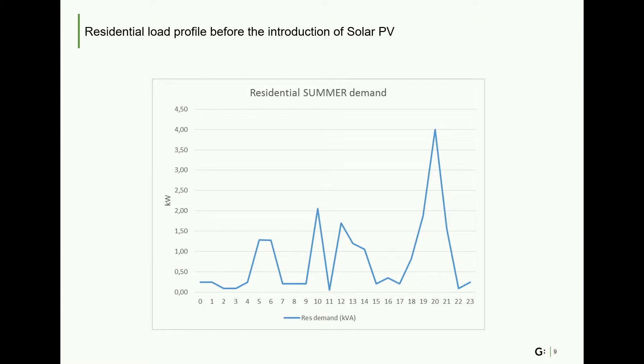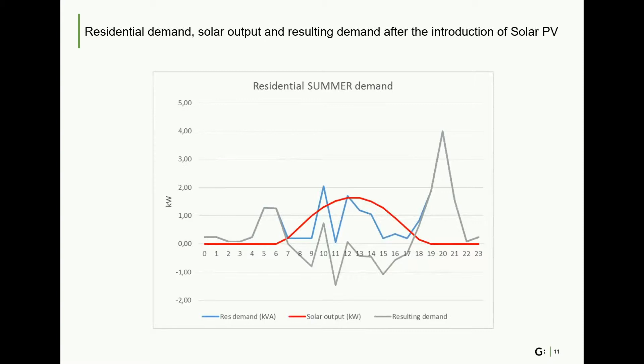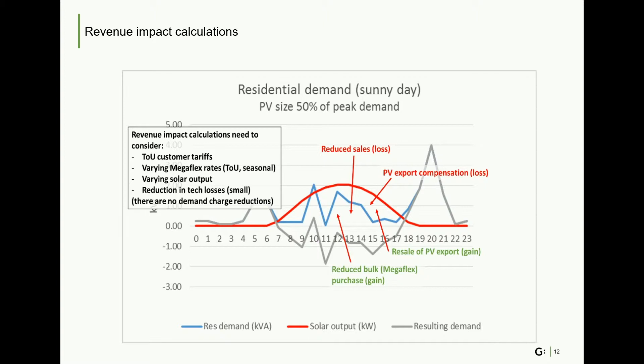Now this house has installed rooftop PV. This chart shows the original consumption profile, which is the blue line, the solar PV output, which is the red line, and the resulting demand, which is the grey line. Where resulting demand is negative, this means that production of electricity exceeds supply and the customer will want to export that electricity back onto the grid. Where demand is positive, the customer will import electricity from the grid to supplement their own generation. The municipality needs to purchase less power from Eskom and thus this is a cost saving.